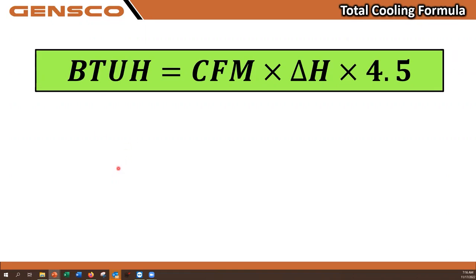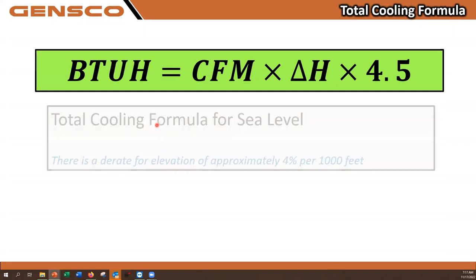This is the formula for doing a total cooling BTU-H calculation. It's similar to our previous sensible in that we still use CFM. We still have a constant. In this case, it's 4.5. And we're going to be dealing with the difference in enthalpy of the air coming in and the air going out of the unit. The enthalpy is the BTUs per pound that's actually in the air. And we want to see a difference of that enthalpy. And we're going to show you that calculation shortly.